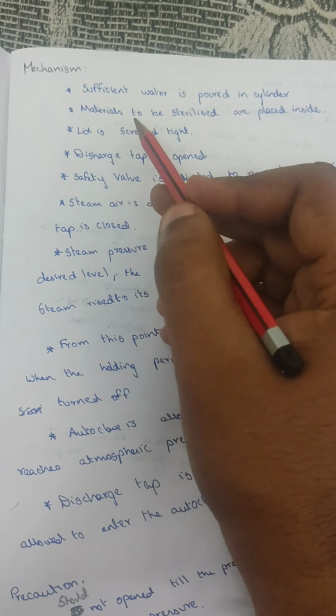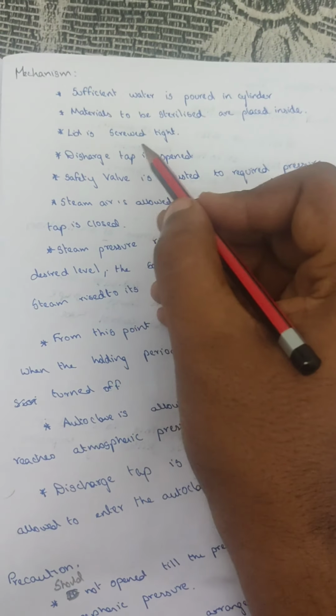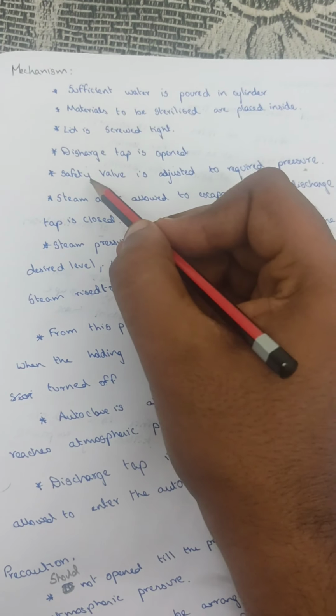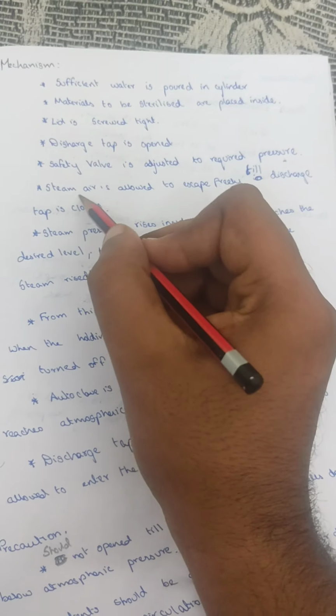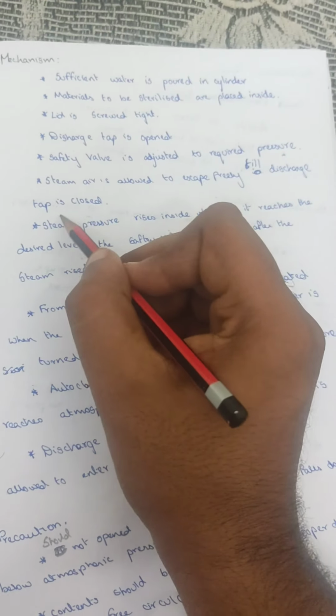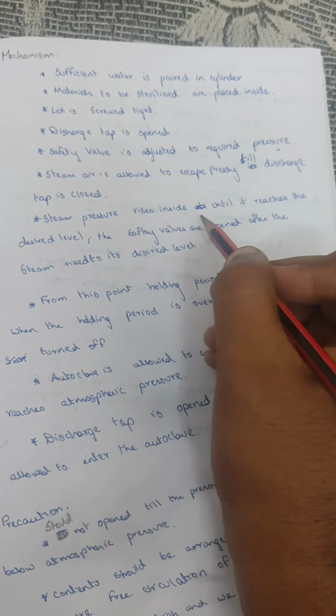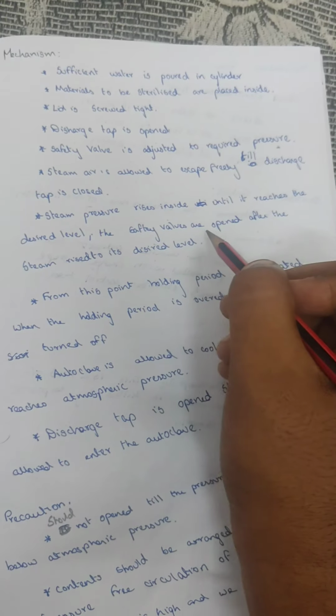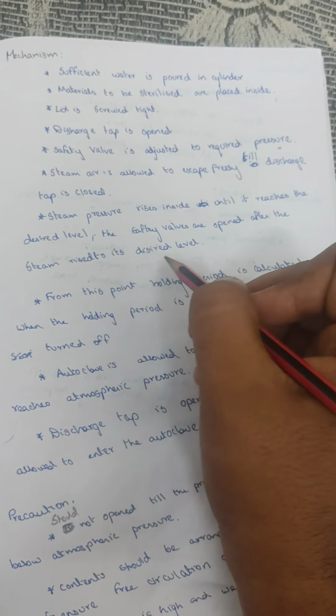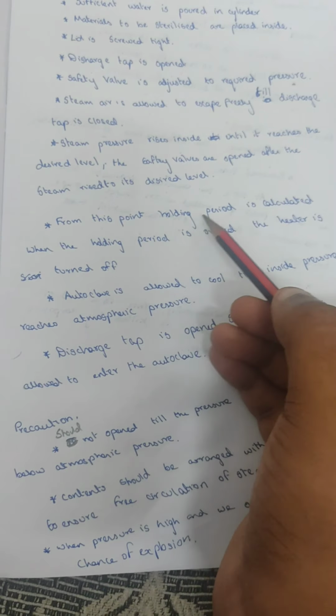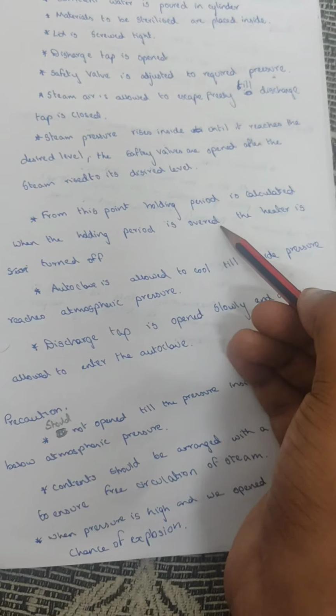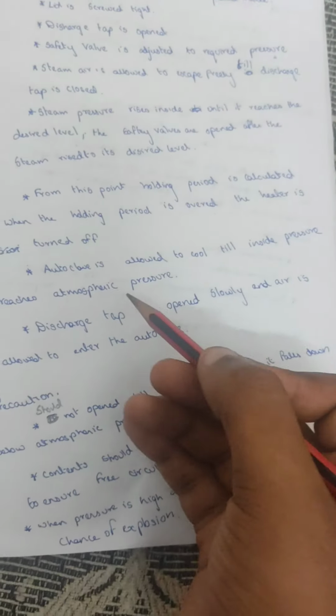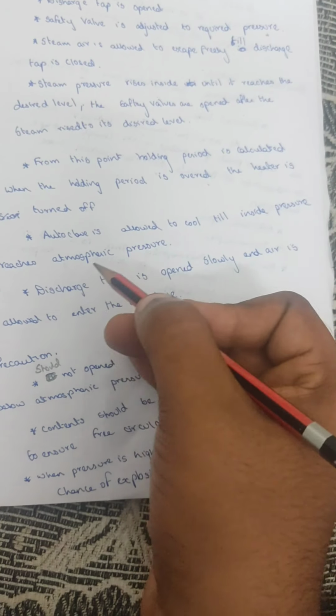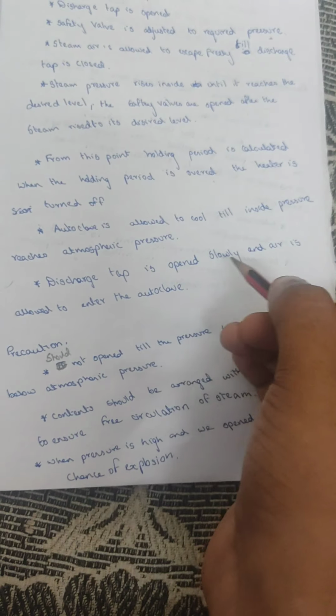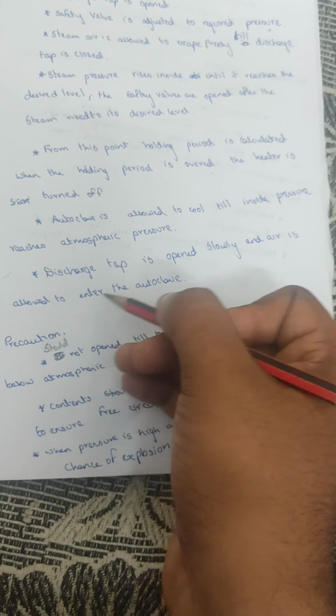Mechanism: sufficient water is poured in the cylinder. Materials to be sterilized are placed inside. The lid is screwed tight. The discharge tap is opened. The safety valve is adjusted to the required pressure. Steam and air are allowed to escape freely till the discharge tap is closed. Steam pressure rises inside until it reaches the desired level. The safety valve is opened after the steam is raised to the desired level. From this point, the holding period is calculated. When the holding period is over, the heater is turned off. Autoclave is allowed to cool inside, and the pressure reaches atmospheric pressure. The discharge tap is opened slowly and air is allowed to enter the autoclave.